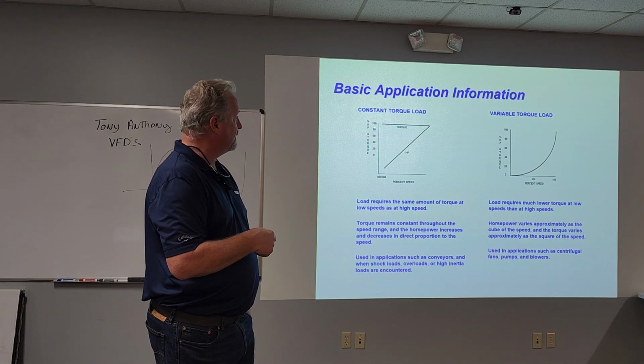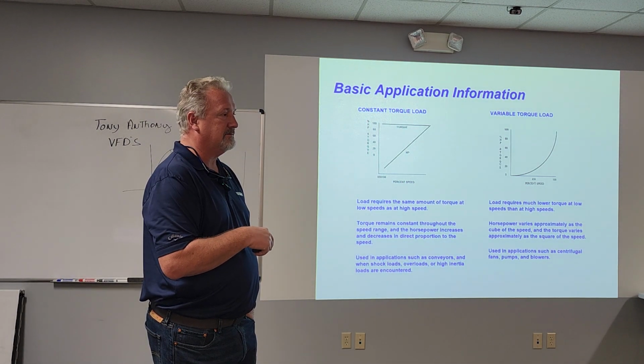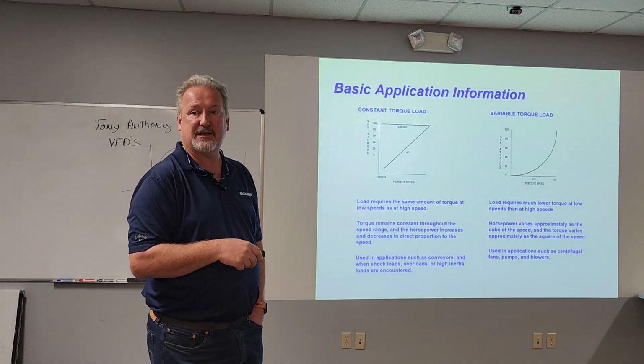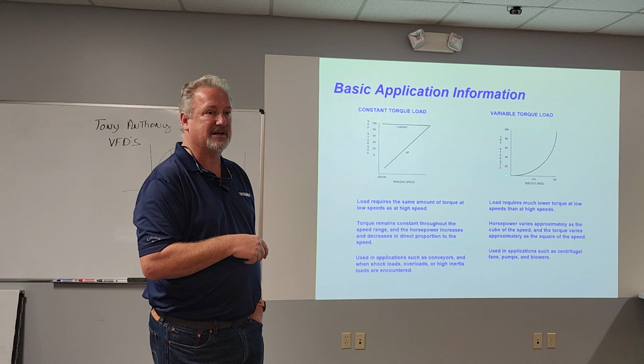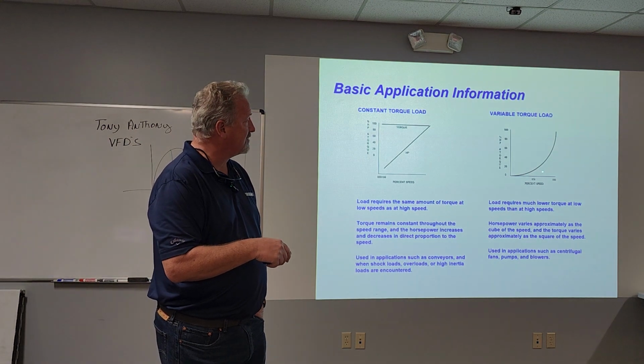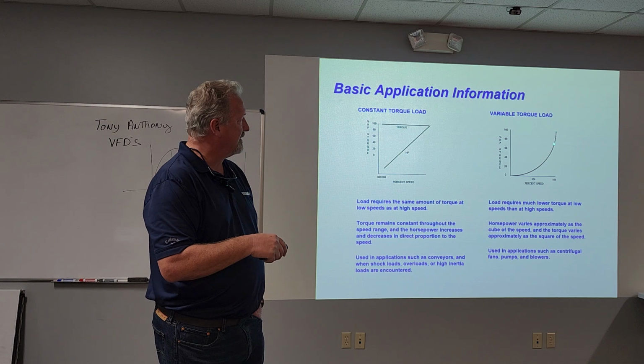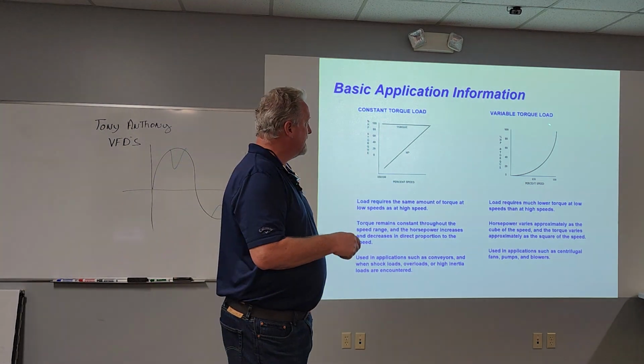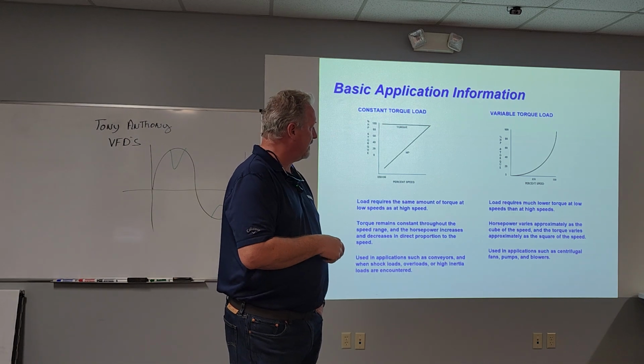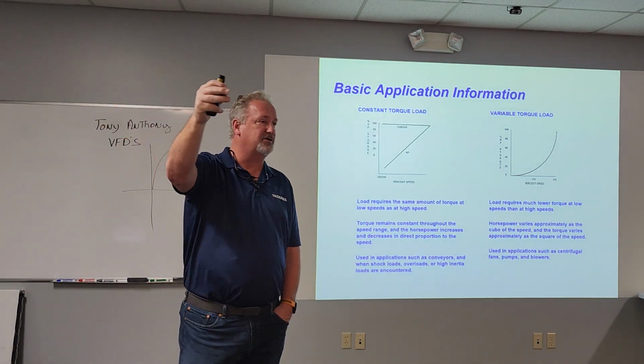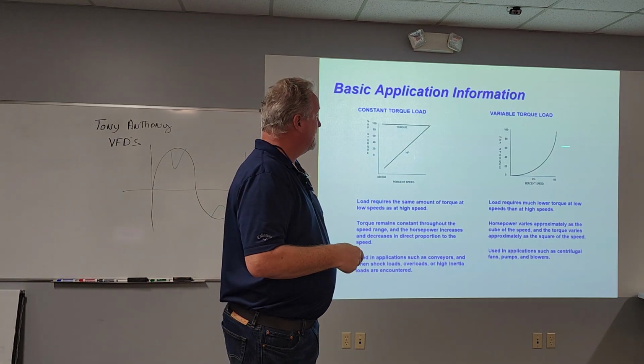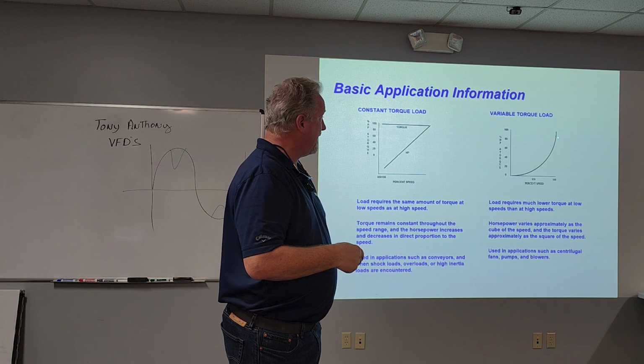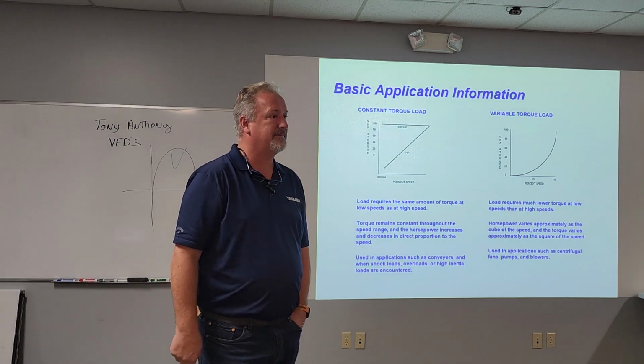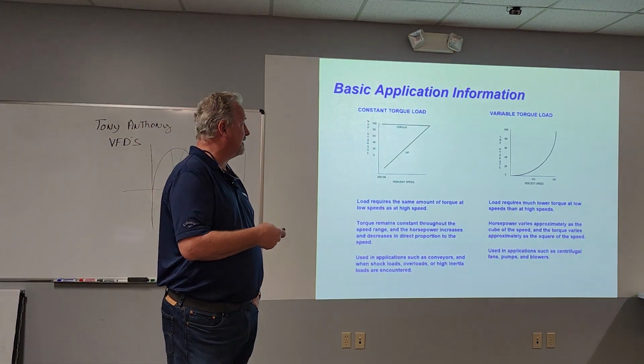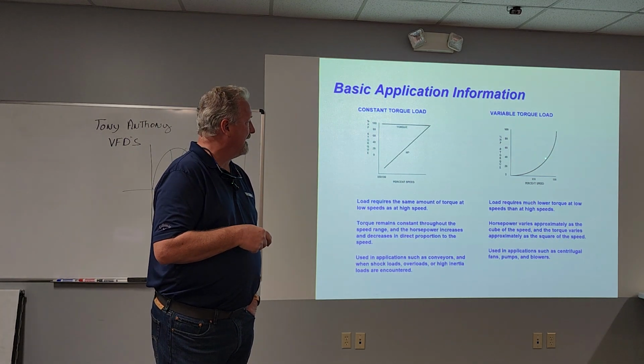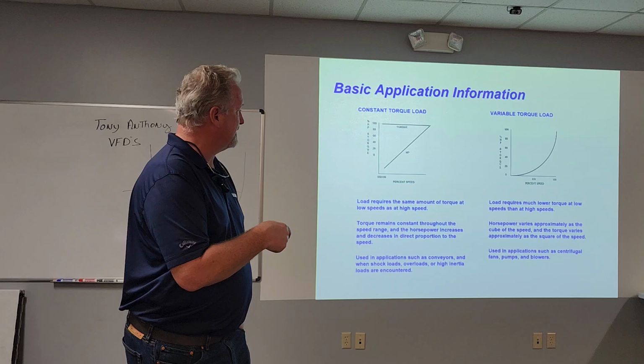To get this going, we need a little extra oomph at the bottom. So these drives are rated for 150% overload. Your HVAC drives are rated only for 110% because we should never exceed that at all, since it takes nothing to get going. But the faster we go, out here to 100% speed, 60 hertz, this is almost a straight line up and down. This is where we can save a lot of energy, because with variable torque loads, the faster it goes, the more torque and power it takes to run that fan. The rule of thumb: if you can slow that fan or that pump down 20%, it saves 50% of the energy to run that motor. It's due to the affinity laws, which we'll discuss here in a second.